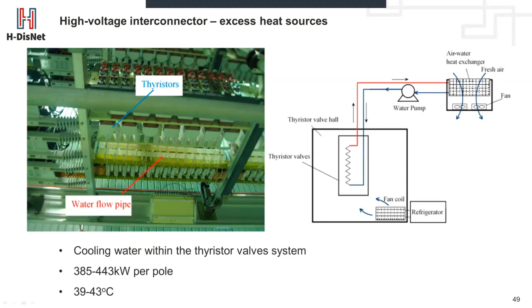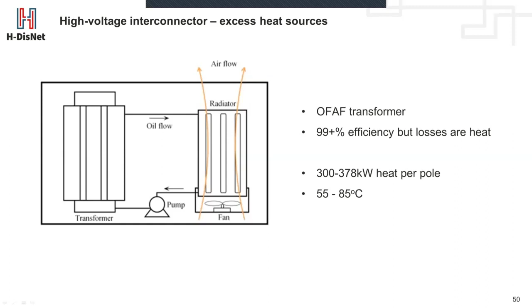There's a cooling system which cools down the transformer, and that again is between 300 and 378 kilowatts of heat per pole, at a slightly higher temperature. Obviously, again, it is a very high efficiency process in electrical terms, but when you strip it back and do it at a large enough scale, there's a lot of heat being generated that can be utilized. And the idea was that we used the heat to drive the desiccant system, and the desiccant system would then be used to offset the air conditioning requirement for the thyristor hall.